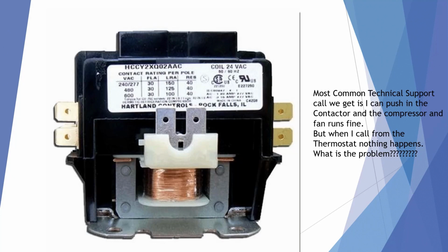The most common technical support call we get is, "I can push in the contactor and the compressor and fan run fine. But when I call for the thermostat, nothing happens. What's the problem?"